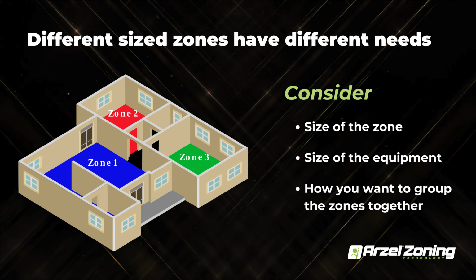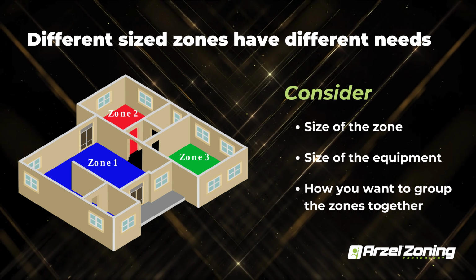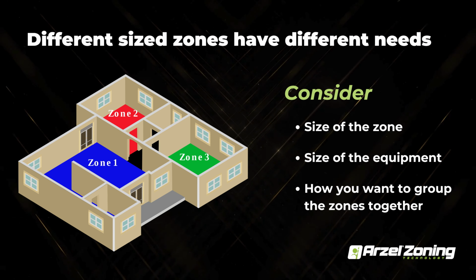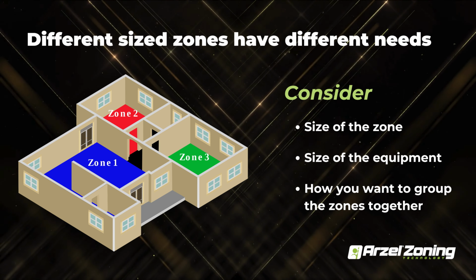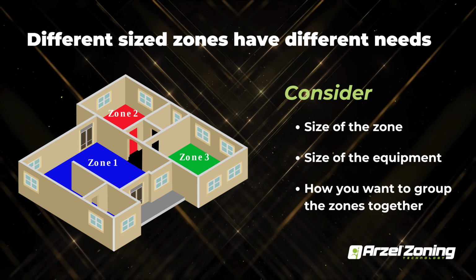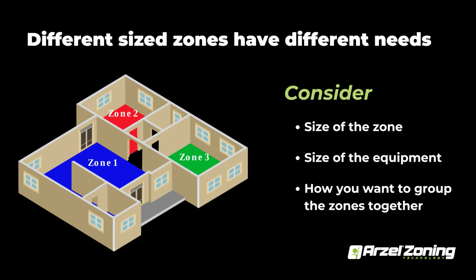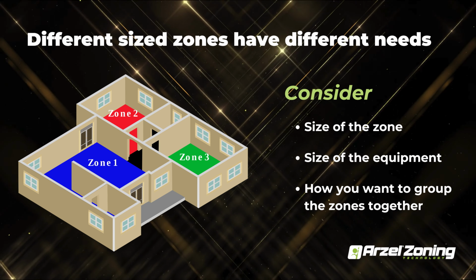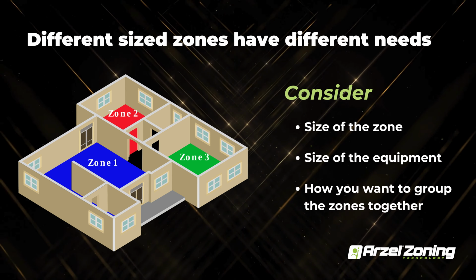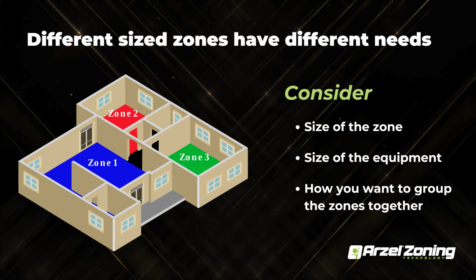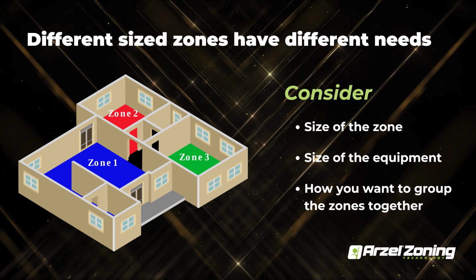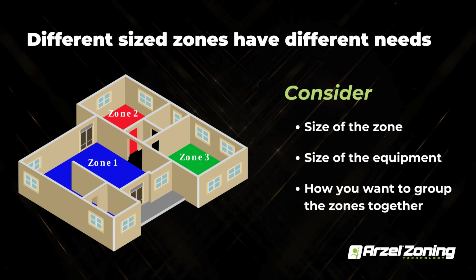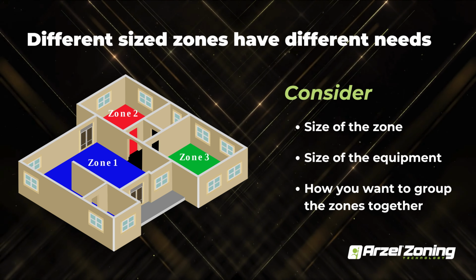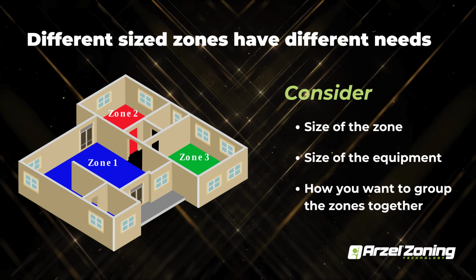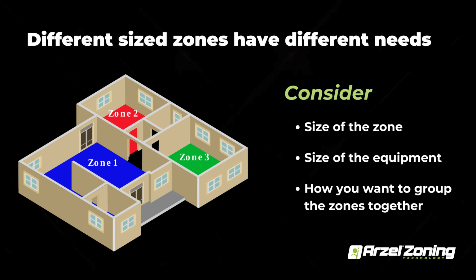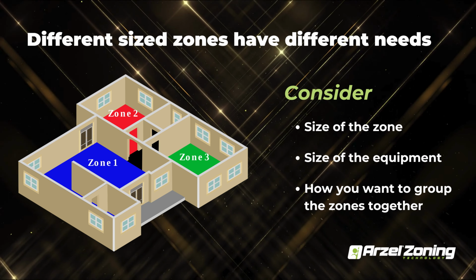So there's really three things to keep in mind when you're breaking up a home into zones: what size is the zone, what size is your equipment, so how much CFM we're actually supplying to the zone, how big your equipment is in tonnage, and that's going to be your blower motor tonnage, and then which zones you want to actually group together. Those are the biggest things you want to consider with zoning. So one of the big things is, can your equipment actually handle Y1, Y2 operations? Can it handle a second stage operation, or is it too small to handle that full CFM output?